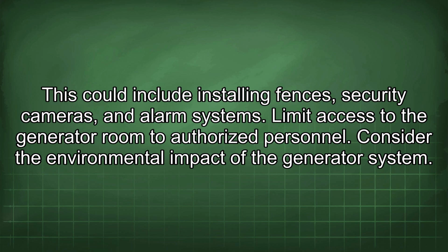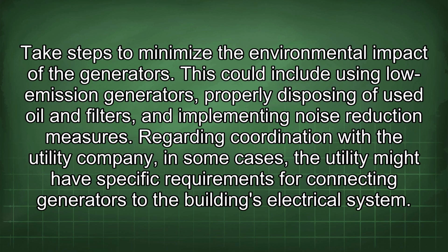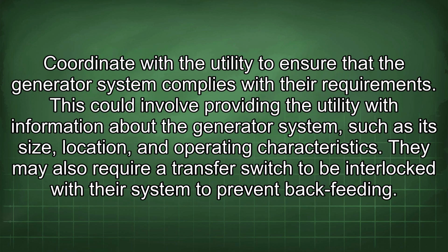Consider the environmental impact of the generator system. Take steps to minimize the environmental impact of the generators. This could include using low-emission generators, properly disposing of used oil and filters, and implementing noise reduction measures. Regarding coordination with the utility company, in some cases, the utility might have specific requirements for connecting generators to the building's electrical system. Coordinate with the utility to ensure that the generator system complies with their requirements. This could involve providing the utility with information about the generator system, such as its size, location, and operating characteristics. They may also require a transfer switch to be interlocked with the system to prevent backfeeding.